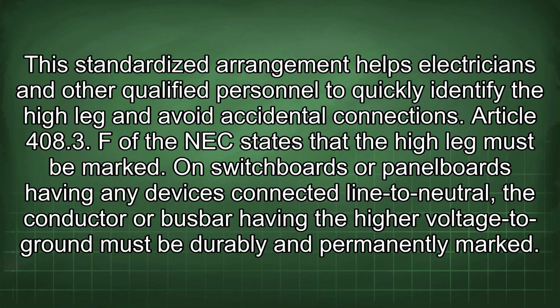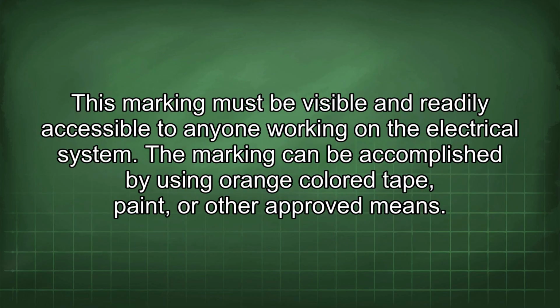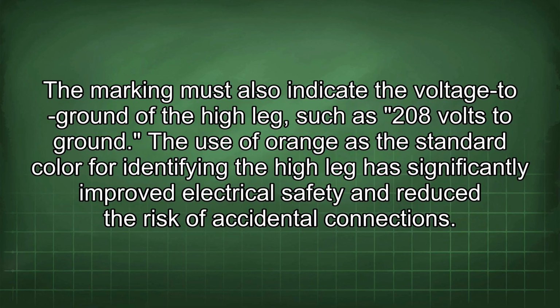Section 408.3(F) of the NEC states that the high leg must be marked. On switchboards or panel boards having any devices connected line to neutral, the conductor or busbar having the higher voltage to ground must be durably and permanently marked. This marking must be visible and readily accessible to anyone working on the electrical system. The marking can be accomplished by using orange-colored tape, paint, or other approved means. The marking must also indicate the voltage to ground of the high leg, such as 208 volts to ground.